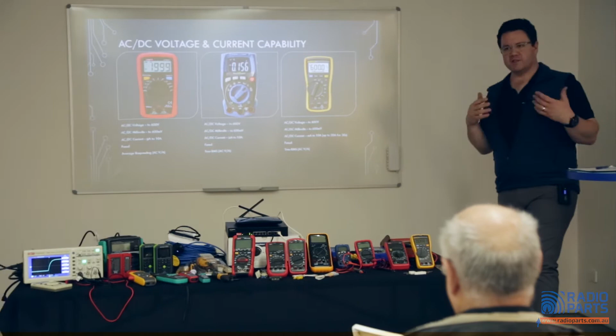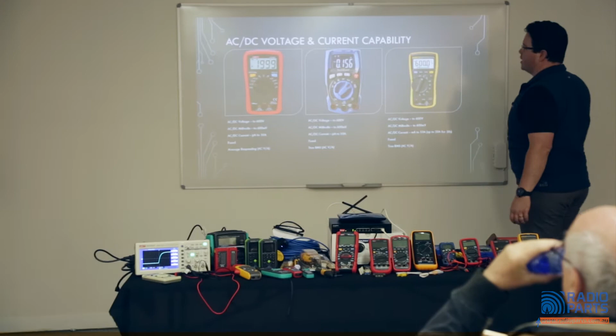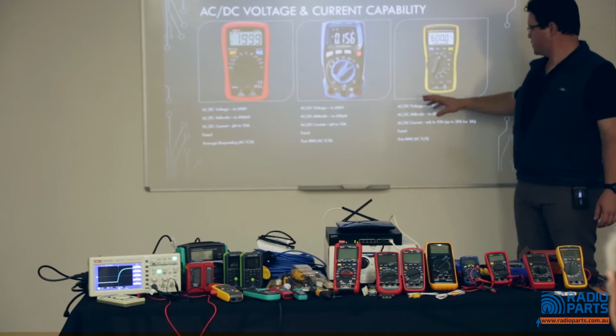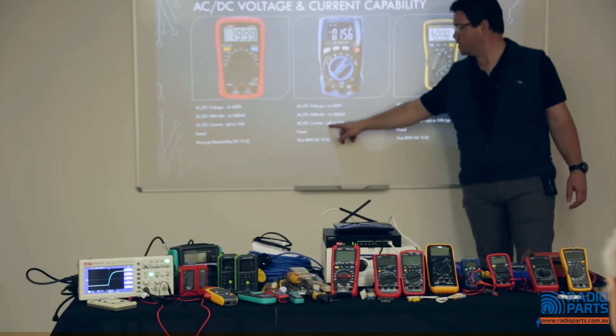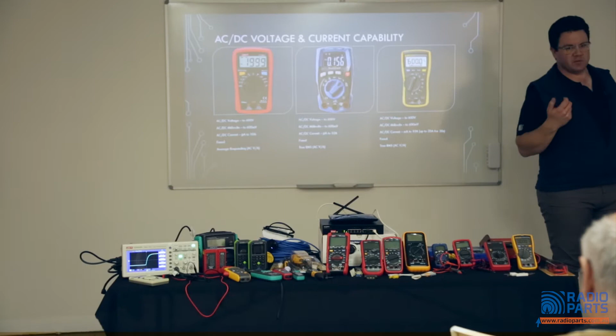There are mining rated ones, there are explosive rated ones, there are multimeters for your purpose. Looking at these ones for AC/DC voltage and current capability, these three are almost identical if you look through most of their specs. The ones I'll spot here, these two both have microamp ranges on them, for really tiny little current measurements—again, probably circuit work more than anything else. This one's only down to the milliamp range, but it will actually take up to 20 amps for 30 seconds, so it's designed and tested for that purpose.